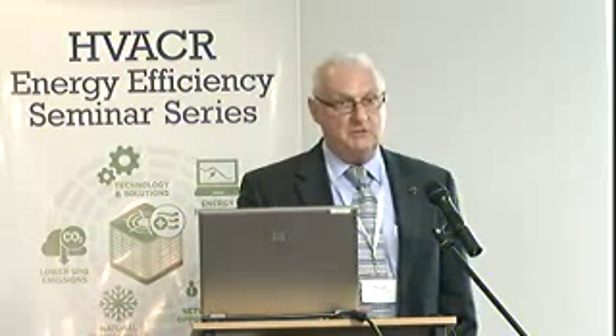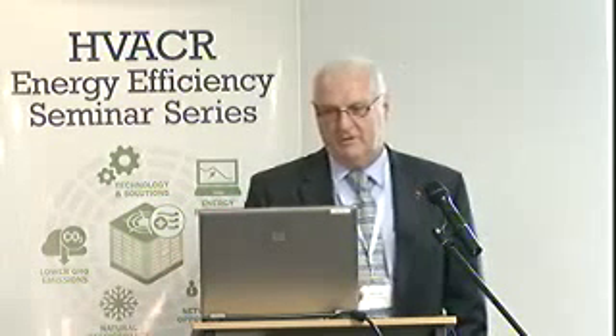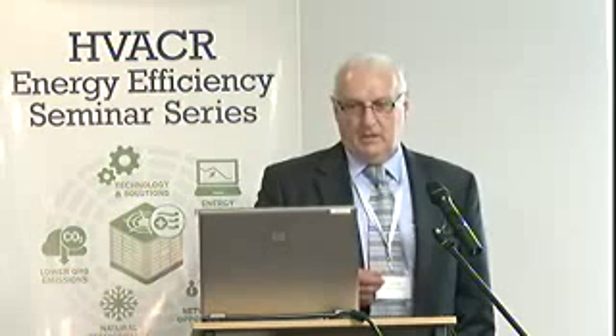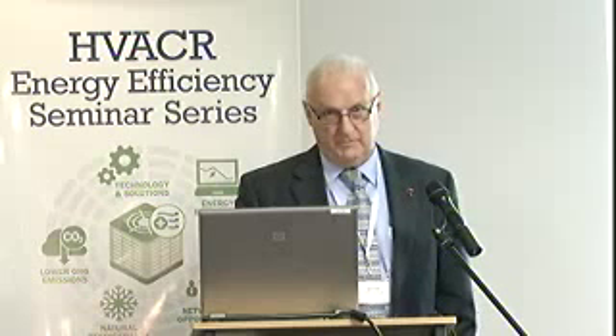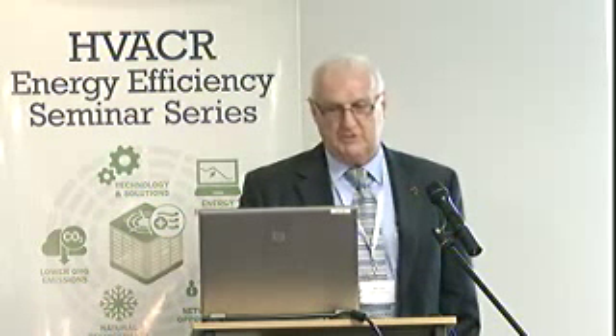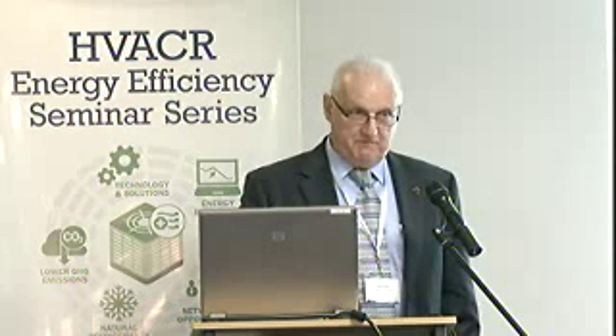So now some absolute facts. Optimisation of supply voltage amplitude will normally reduce energy consumption of inductive loads, motors in particular. Also magnetically ballasted lighting, if there's any still out there that's not being changed out. The reduction varies depending on the average reduction in the voltage that's achieved, the stability of the reduced voltage, the ability to balance the phase voltages, and we'll address some of these in a moment, and the type of electrical equipment connected. It is not the same as power factor correction.